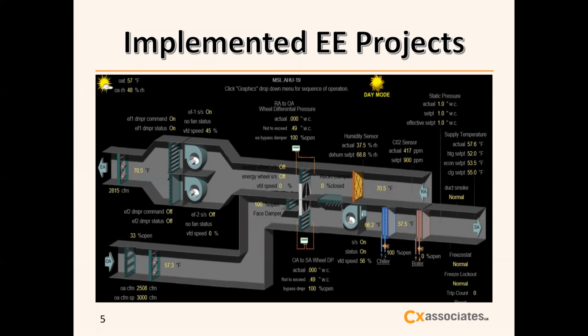As an example of this last one, the event spaces: for these spaces, the new automated control system enabled the event coordinator to set space temperatures to the schedule of the events rather than holding the space at a comfort level during unoccupied hours. Additionally, we enabled the event coordinator to program the event space temperature separately from the ventilation. The temperatures are now set to a comfortable level a few hours prior to an event or when a few people are setting up the space. But we don't increase the ventilation until the event is scheduled to start and people are actually gathering in the space. This saves considerable amount of energy.